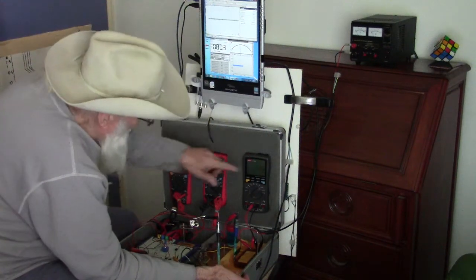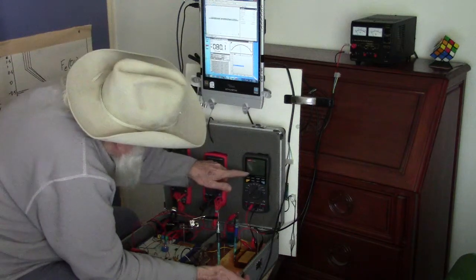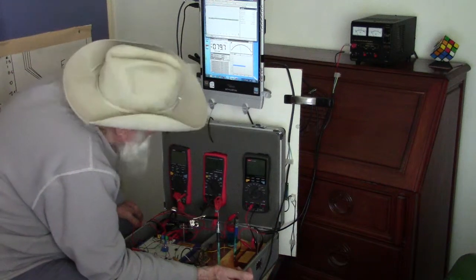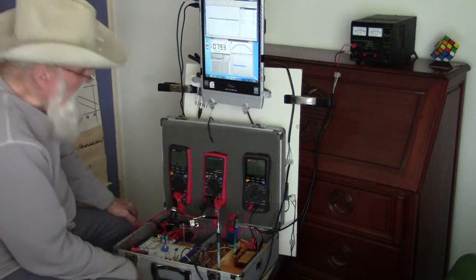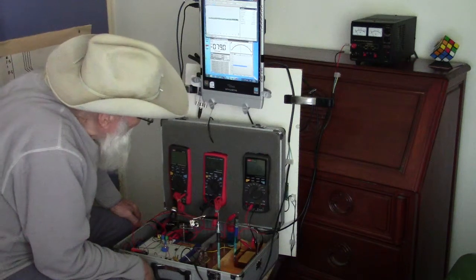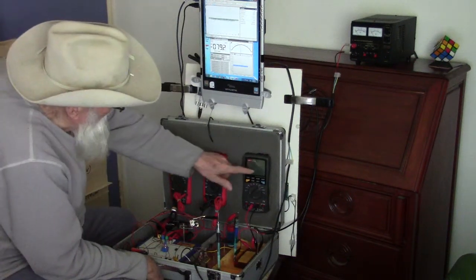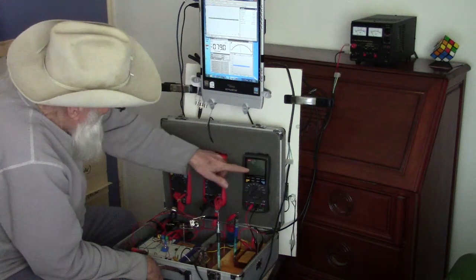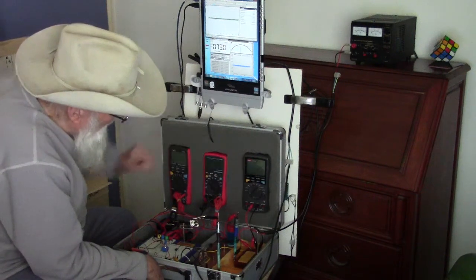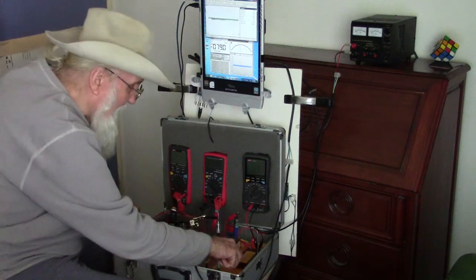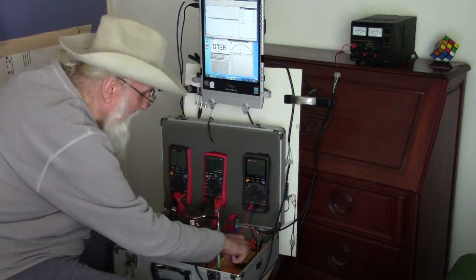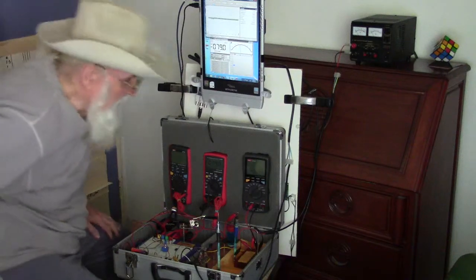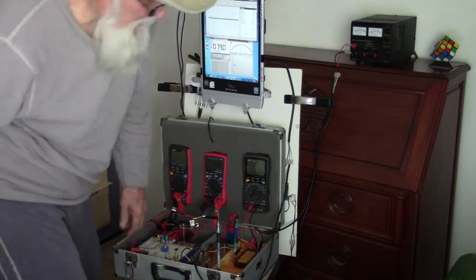I don't know what caused that, but this is corrosion current shown on here, and the negative reading means that it was being protected. So in other words, the corrosion was being stopped. Now, the corrosion is continuing now. And this is the value of the corrosion current passing from the anode of the corrosion cell to the cathode of the corrosion cell. Now what I'm going to do is switch on the cathodic protection.